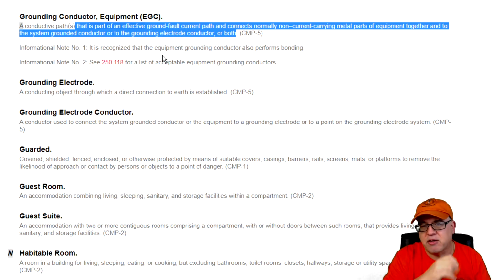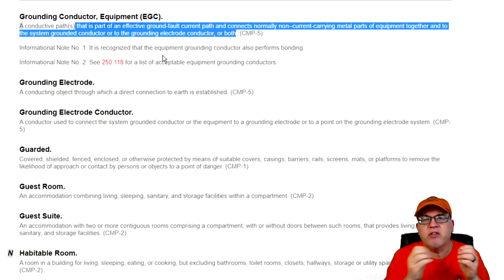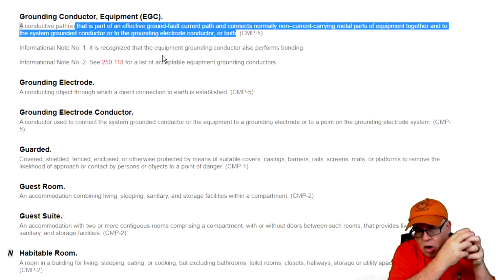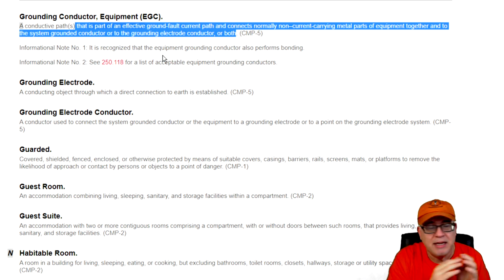And that goes back to the source, which is back at the service, which does have a main bonding jumper, and all of that gets connected to the grounding conductor back at that location, back at the service, not downstream. Okay, so equipment grounding conductors are that little bare wire you see in non-metallic sheath cable. In some cases, for example AC cable, it's the armor. MC, it's not the armor.